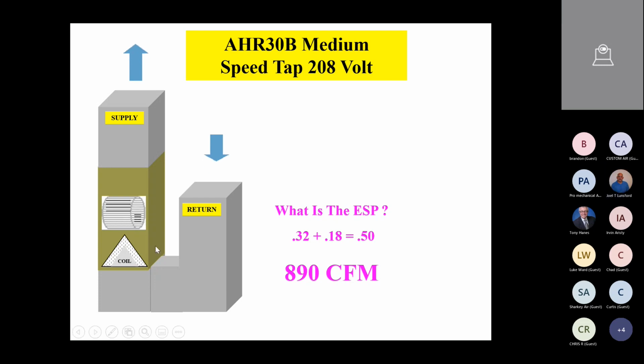Okay. So where do we do this at? And then some units, say it's a different unit, like a Rheem, where it doesn't have a built-in filter rack. There's no place to drill in. You're just going to drill right into the pan. All right. So that's not realistic in the field. So what I would do in those situations, because that's a unique application, I'd make sure I had an absolutely clean coil. In other words, you want that coil clean, clean, clean.